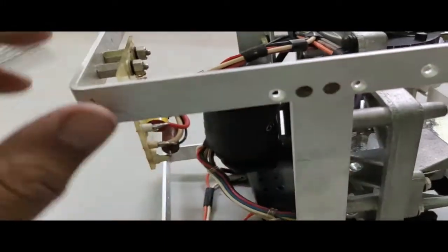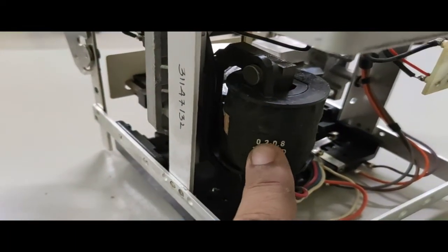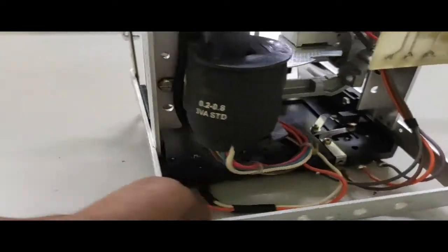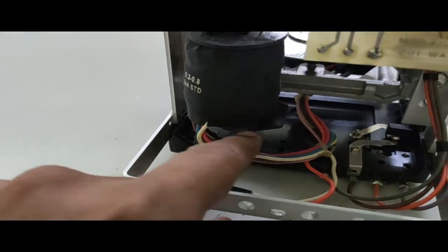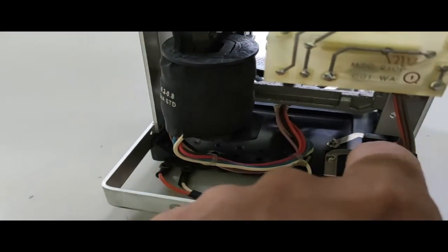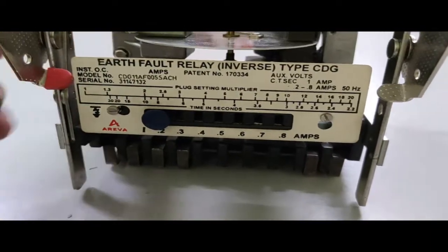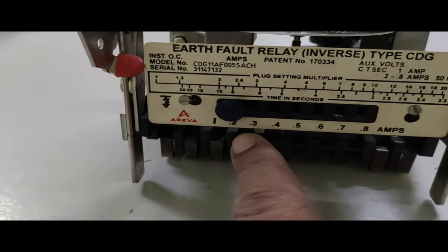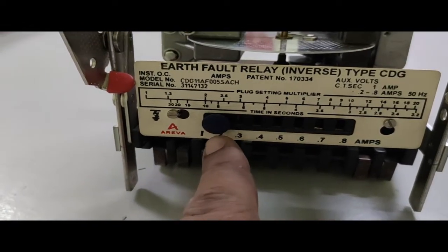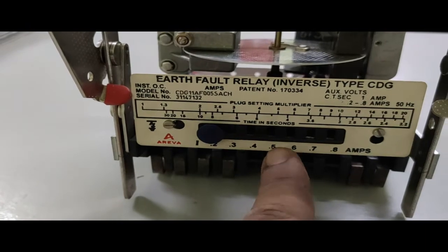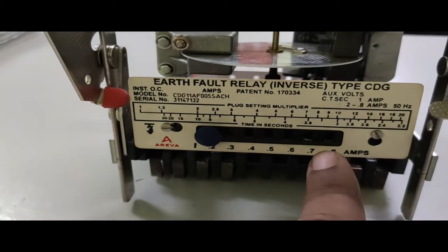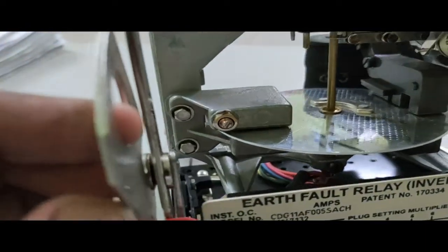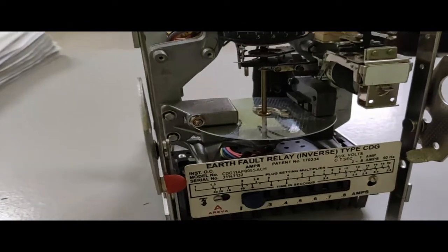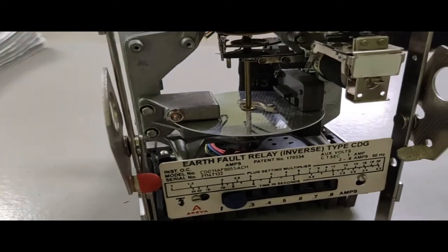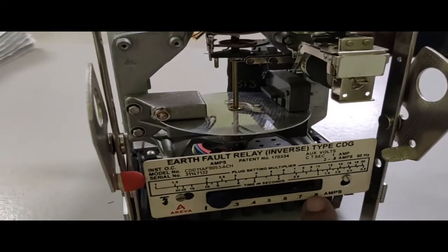Now come to this one. Here you see this is the relay coil, and here you see so many tappings, and these tappings are brought to the front panel, so they are connected here. That means the same relay can sometimes be operated at 0.2 ampere, sometimes at 0.5 ampere, sometimes at 0.8 ampere. So the same relay can be operated according to the requirement of the user. It may be operated at a lower value of the current, and it may be operated at a higher value of the current.